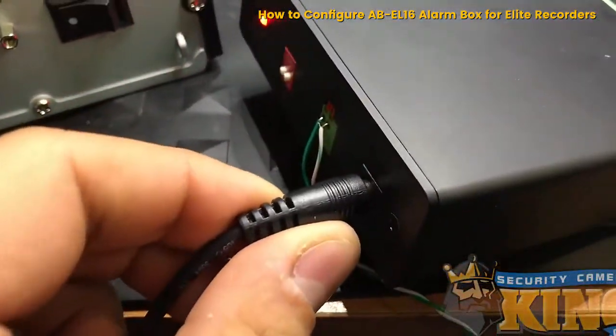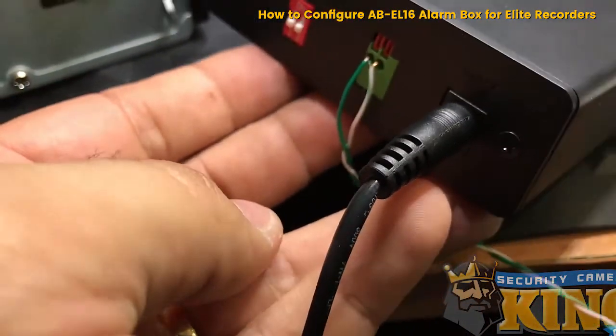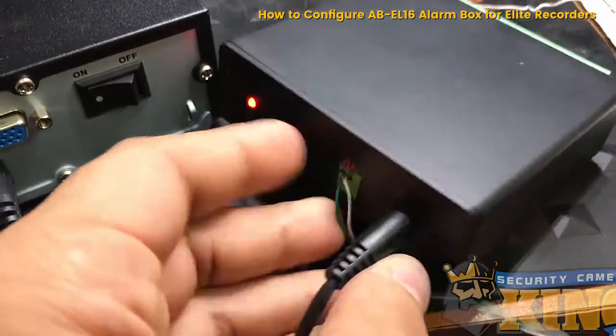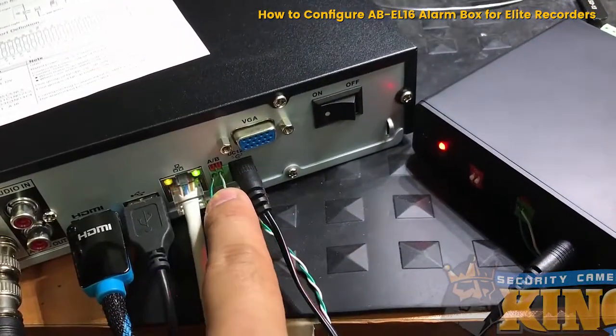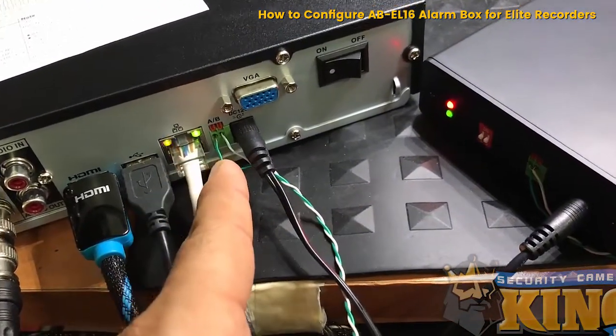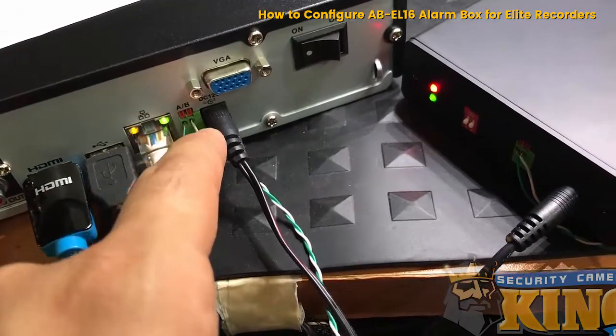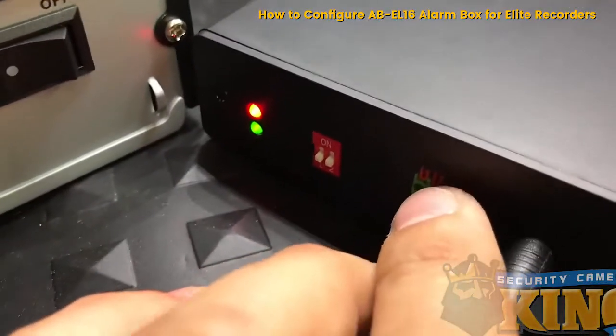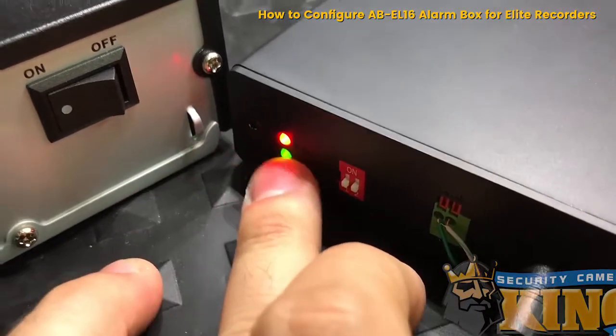Here I have the AB-EL16, which is the alarm box for our Elite series recorders. I have it already connected to an Elite recorder using the RS-485, matching the colors — green and green-and-white, so A would be green and then green-and-white.